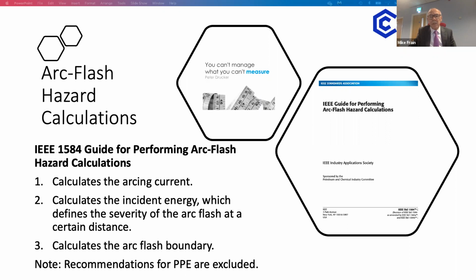And it's this figure that's used for determining PPE requirements and the arc flash boundary. So lastly, an arc flash boundary can be calculated, at which the incident energy is reduced below the figure of 1.2 calories per square centimetre, or 5 joules per square centimetre. So that's that magic figure again, the onset of a second-degree burn. The IEEE 1584 guide does not include any recommendations for PPE to mitigate arc flash hazards, and they're therefore excluded from the scope.